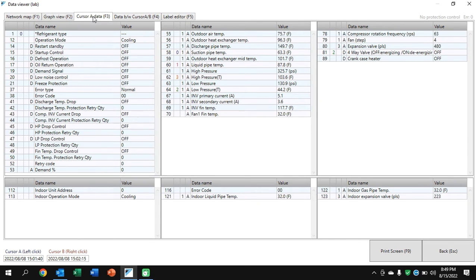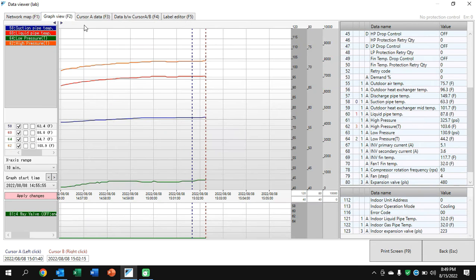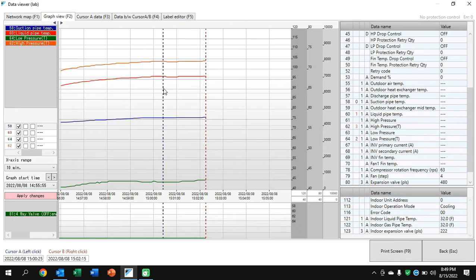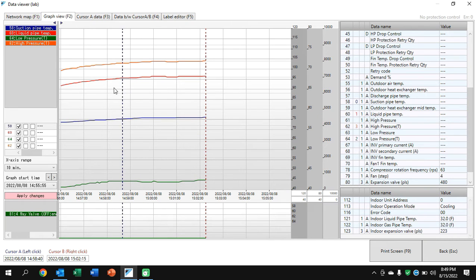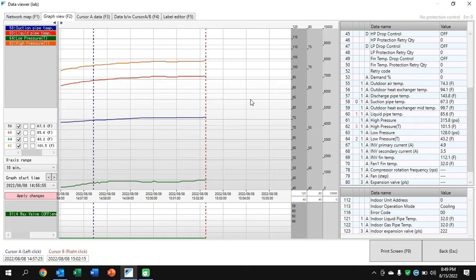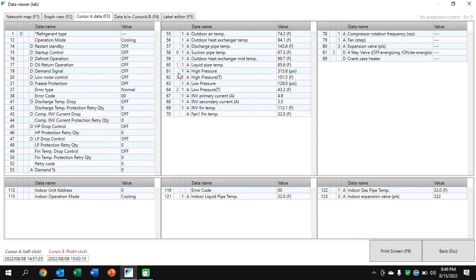Most often when we're working with the data, I'm just looking at the hard numbers and not so much the graph view. But the graph is important because I can move along the timeline. And you see I'm clicking here at the different times and the things are changing. But I can also keep an eye on that protection and the error on the top right there. And see when an error appears. When the error does appear, that is the moment the unit's seen an error. I can look at the data and the data that's producing the error.